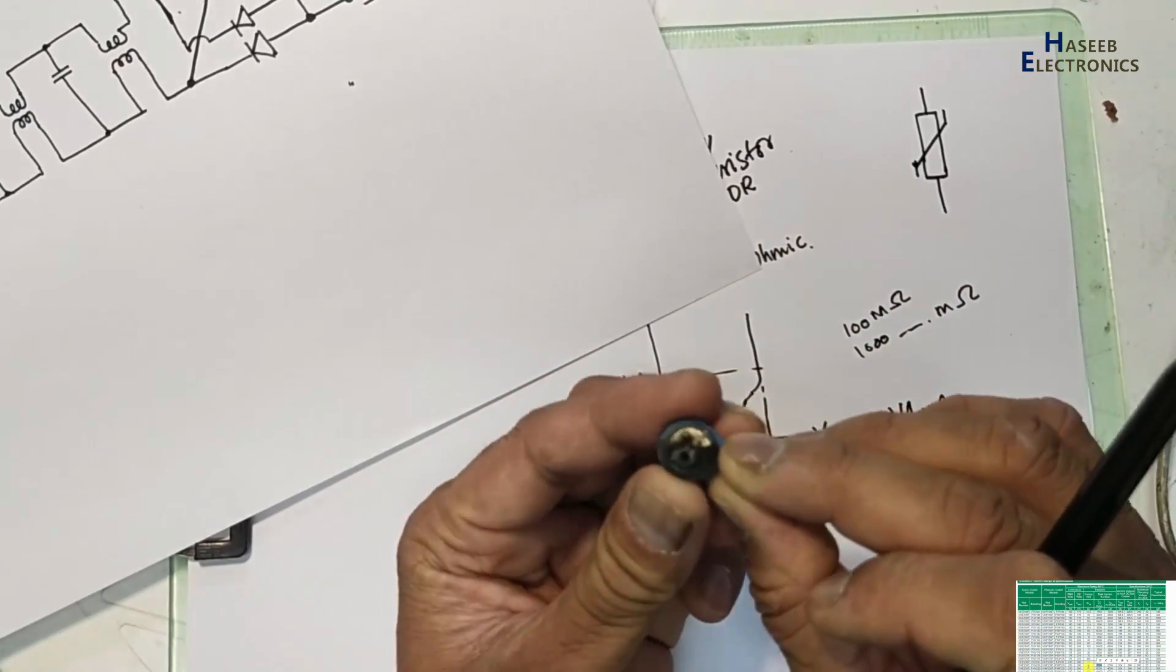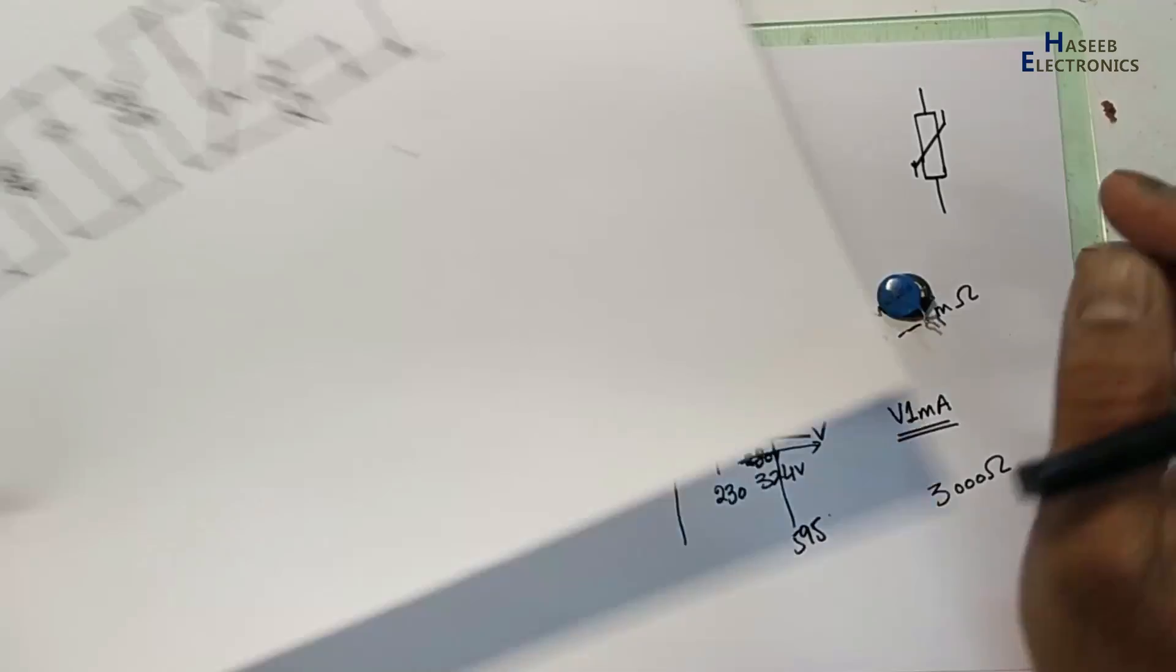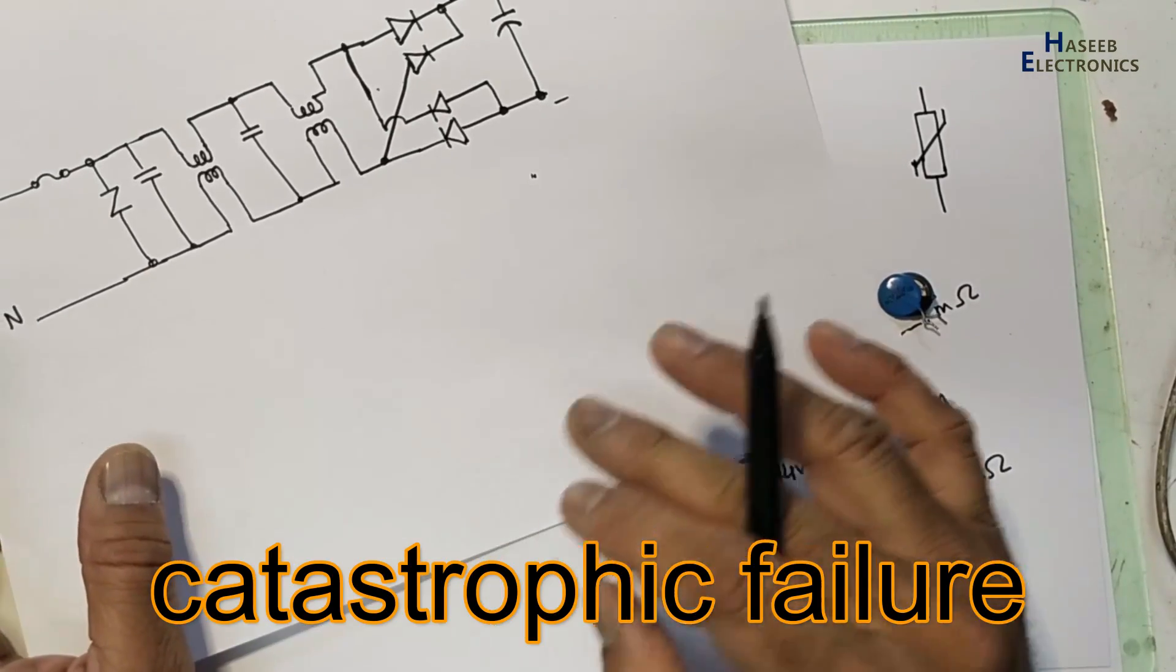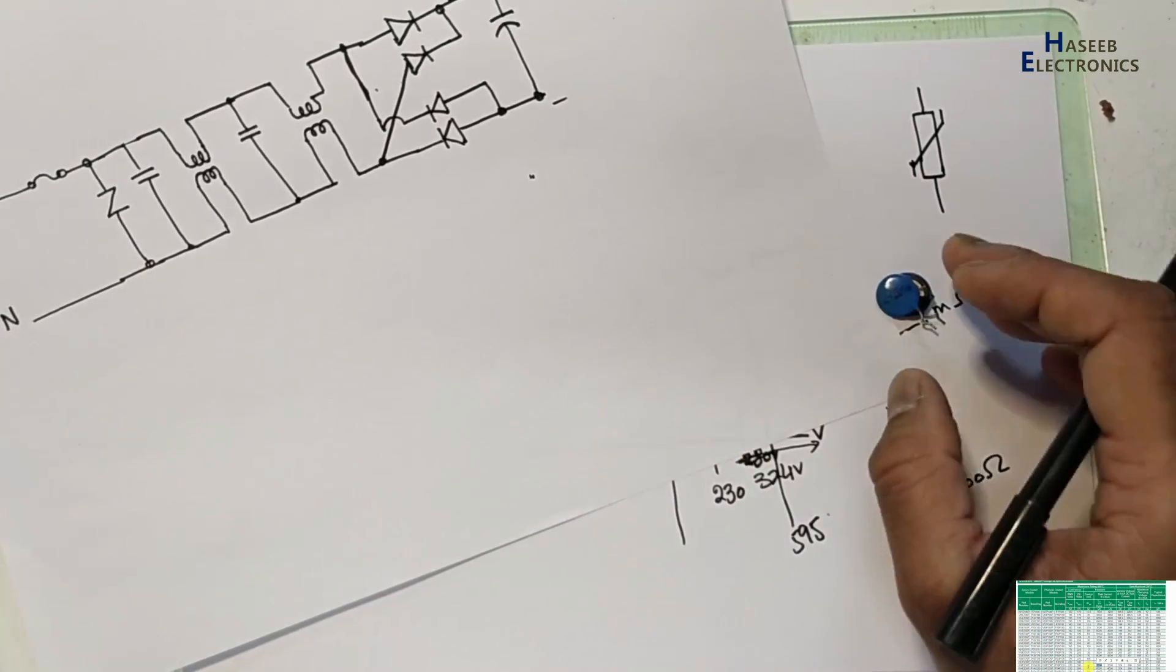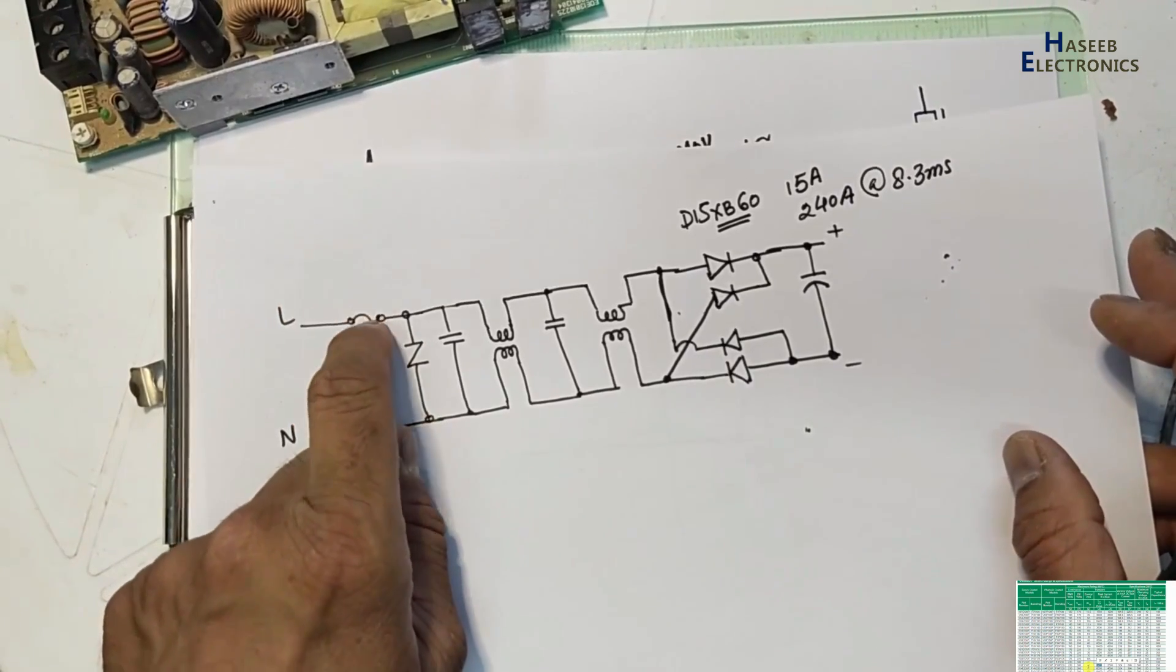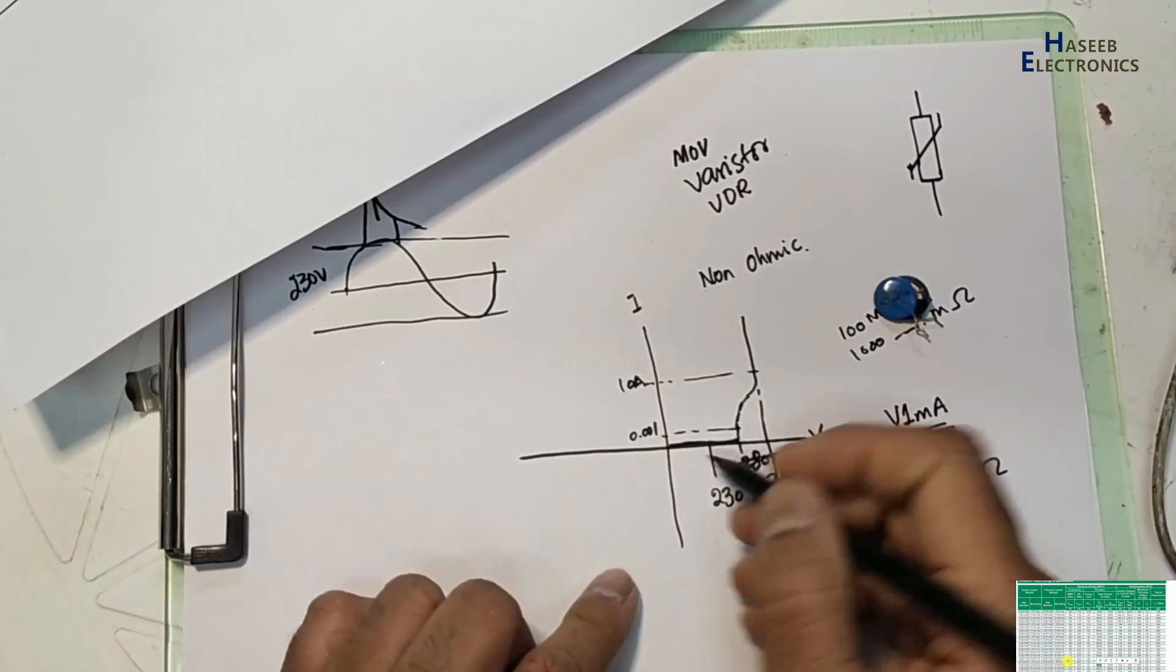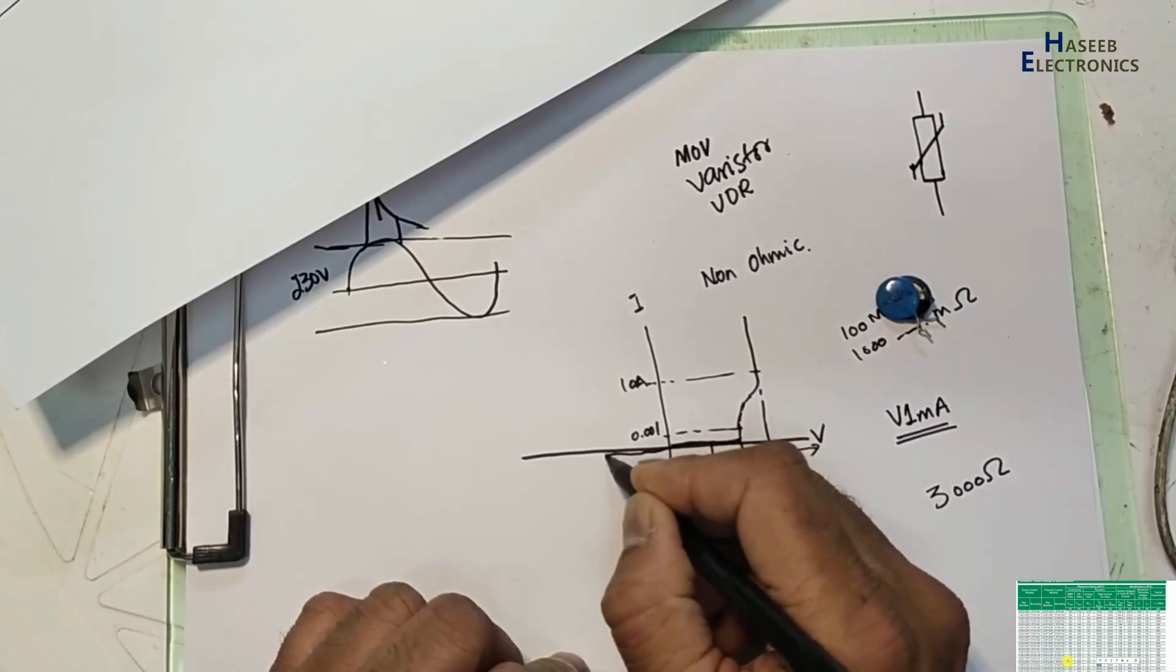When it melts, it will make a short circuit between these two terminals - this one and this one - catastrophic failure. It will damage. In the meantime, the fuse will open. When the fuse opens, the next circuit will be protected. So this responds in both directions.